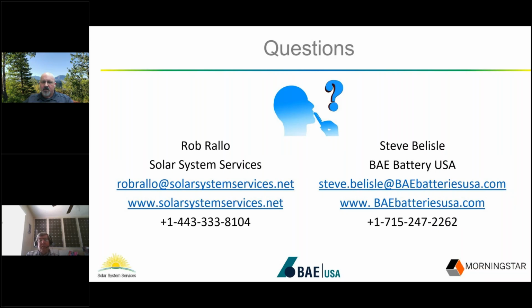I don't know if you want to add to that, Steve. Yeah, you hit the big point, but with a lithium product it depends on what you're dealing with — the thermal runaway event is internally driven, so it doesn't necessarily require an external source, although it can be tied to one. But like Rob says, once it starts, you can't stop it. Whereas lead acid batteries are pretty well known — they don't go into thermal runaway the way lithium-ion can. They can only be driven into thermal runaway by a charging source, which is why the codes are much more favorable to that technology, and becoming more so.